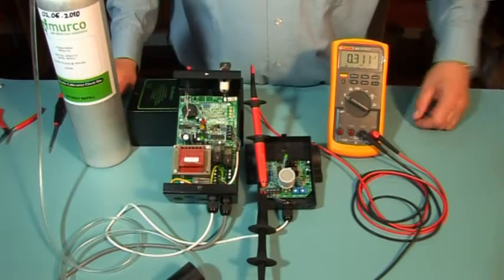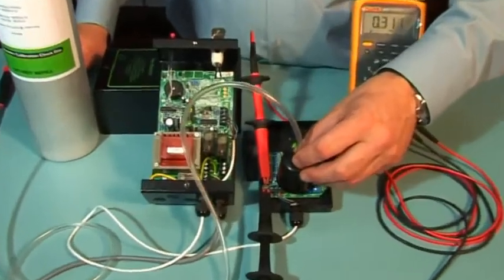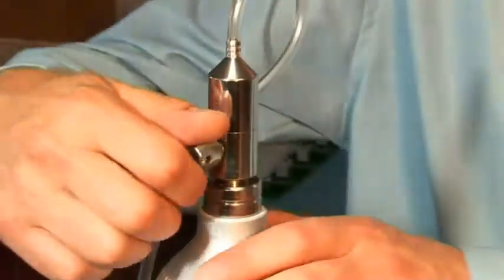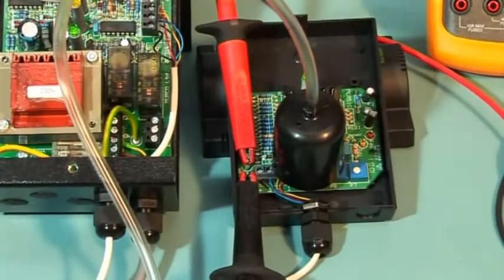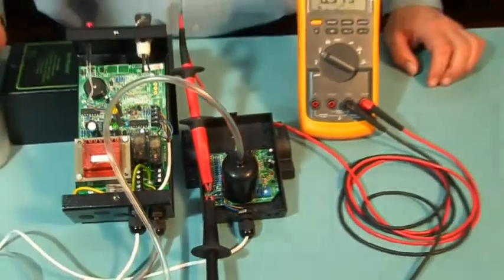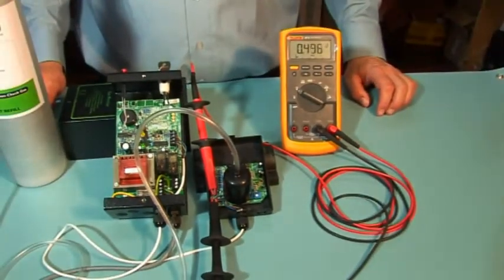Having carried out the electrical setup, expose the sensor to the gas here. You should see the standby voltage increase. It may take 10 to 15 minutes to pass the alarm set point. Older sensors may take longer.